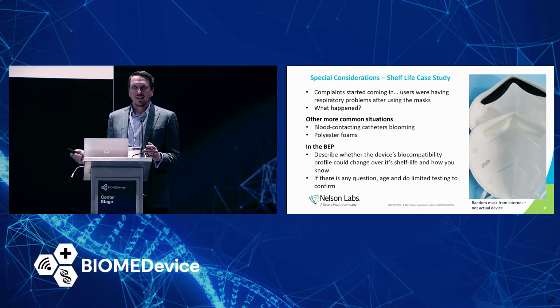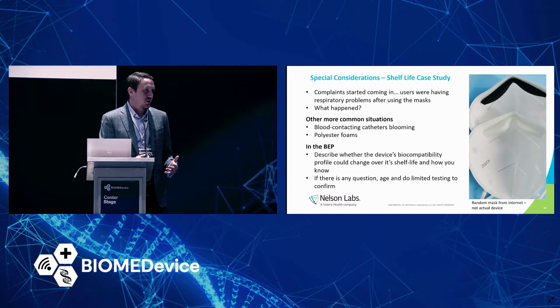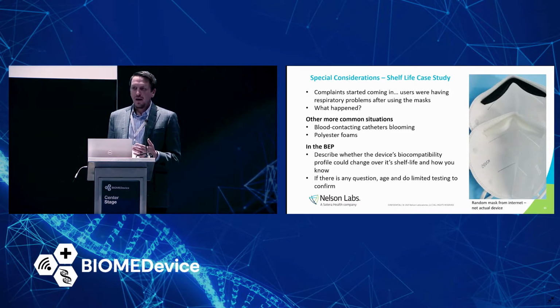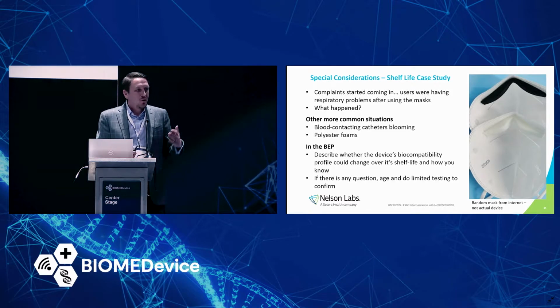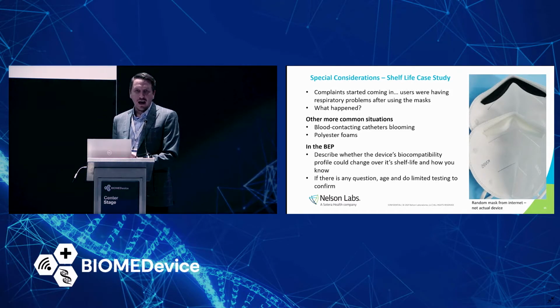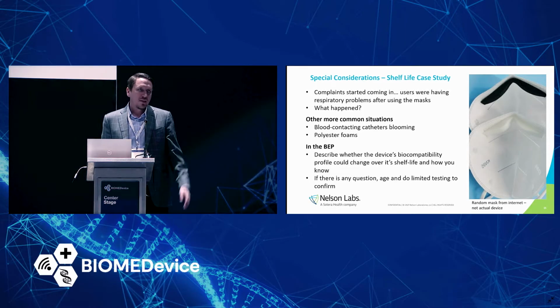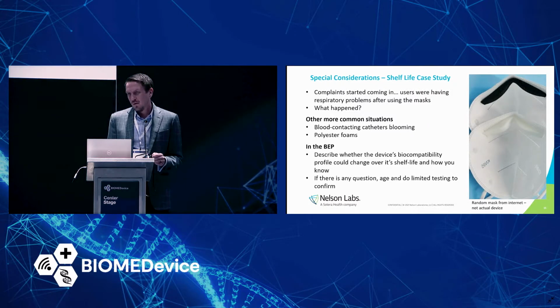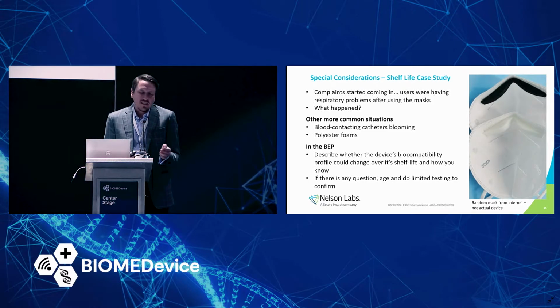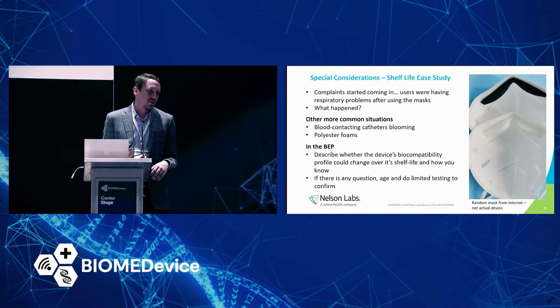Very long story short with this example, in the BEP, this should be considered. So do you know that the biocompatibility of the device is stable over time? If you do know that, why? If you don't know that, what are you going to do to ensure that it is actually stable over time? And in some cases it's super clear. Think about something like a 316L stainless steel knee. So we know the oxidation profile of 316L stainless steel and those characteristics under all sorts of different conditions. And we know that that surface is stable over many years. So that's easy to say, 316 doesn't change as it sits on the shelf.